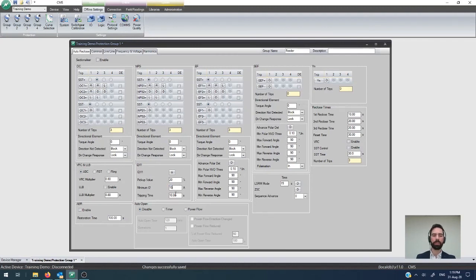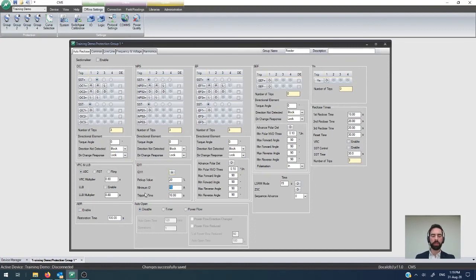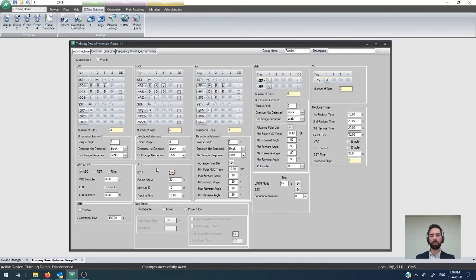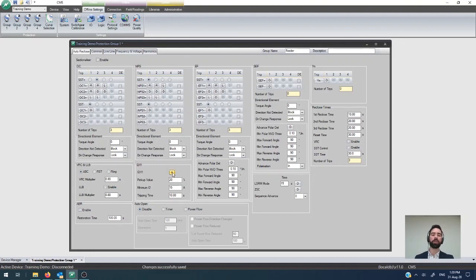With those elements configured there, you are now ready to go to detect broken conductors. Generally, if you're not choosing to lock out on that configuration and you have SCADA available, you would route that back to your SCADA master station so you can use that to tell your operators that there's a broken cable on that line and it certainly needs some investigation.